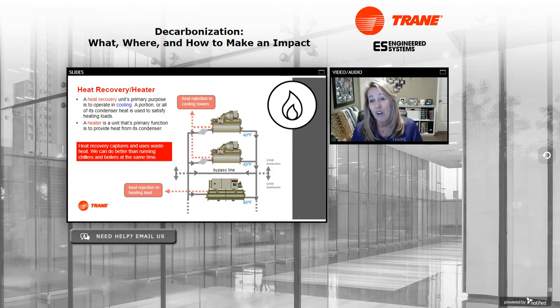Now, chillers can also act as heaters. When a chiller is a heater, its primary function is producing heat. So the chiller is looking at a leaving condenser or hot water set point, and that's what it's controlling to. That chiller, now we're calling it a heater. Sometimes we would call it a chiller heater. I've even heard them referred to as cheaters. Its primary function is to provide heat and control off of that hot water set point.